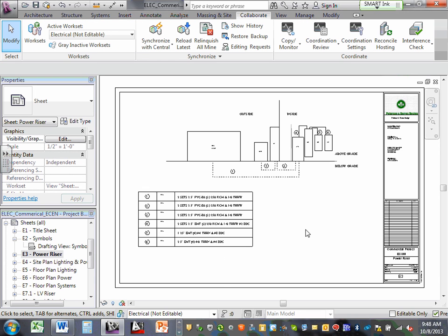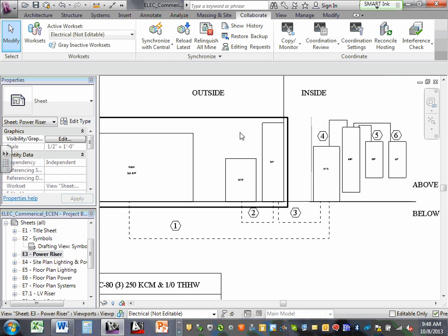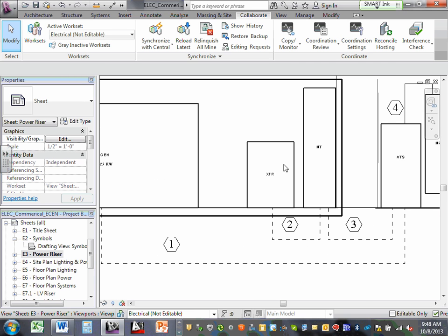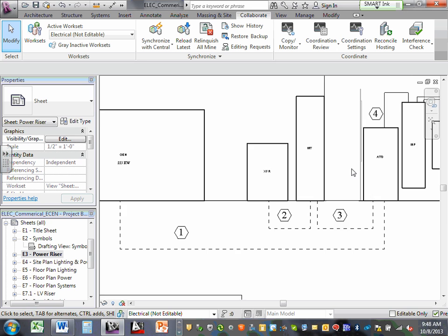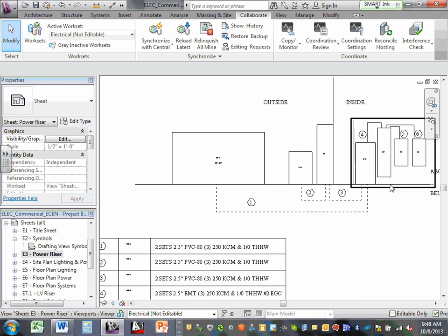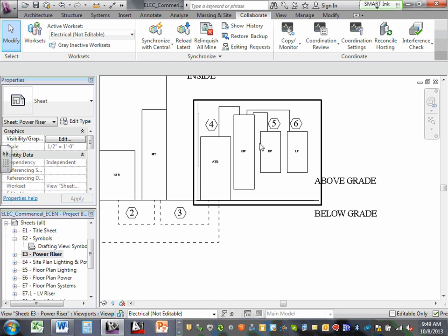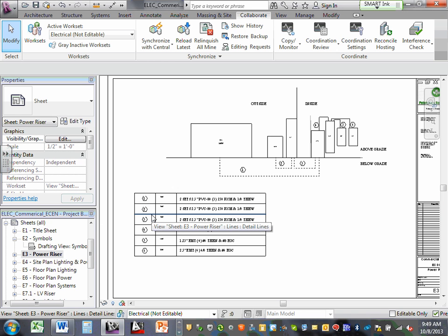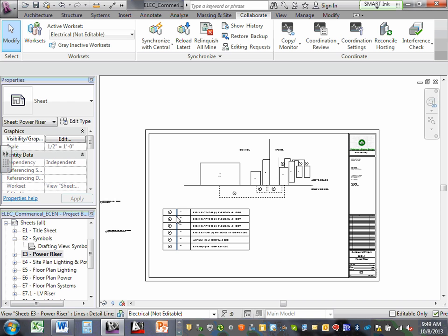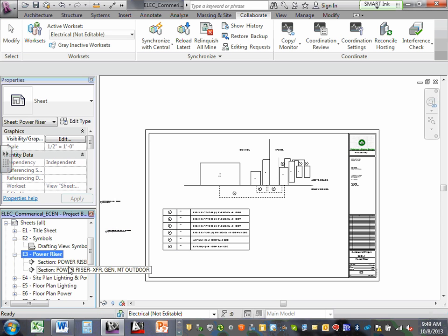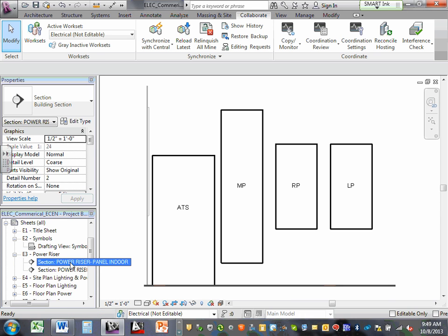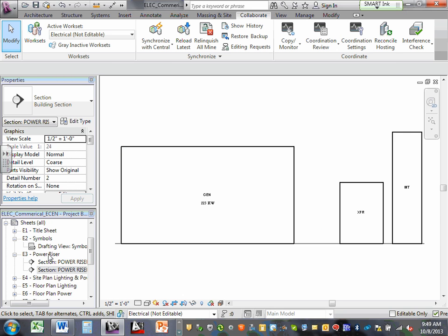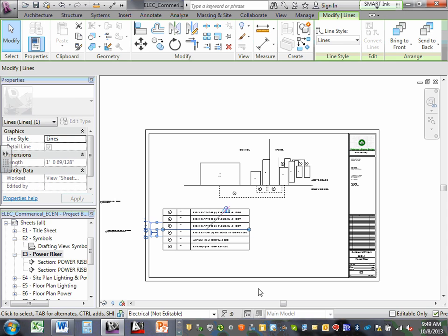Here are all the risers. Your riser is going to look something like this: a generator with a transformer coming to a meter cabinet, out to an ATS, out of the ATS to the main panel, a receptacle panel, and a lighting panel with some text and a schedule. All of what you're looking at are views — they call them sections. There are sections, and the rest is just drafting.